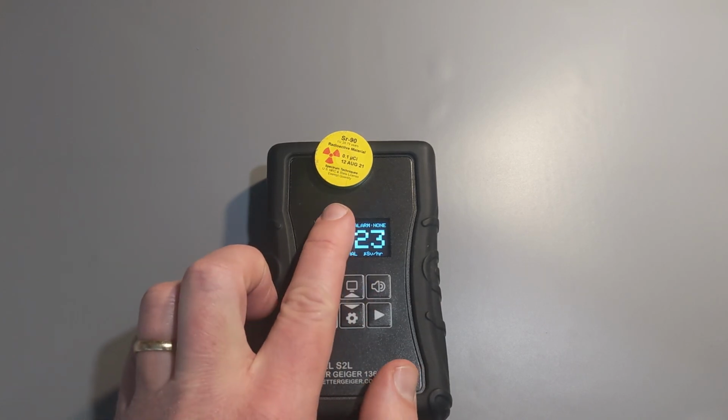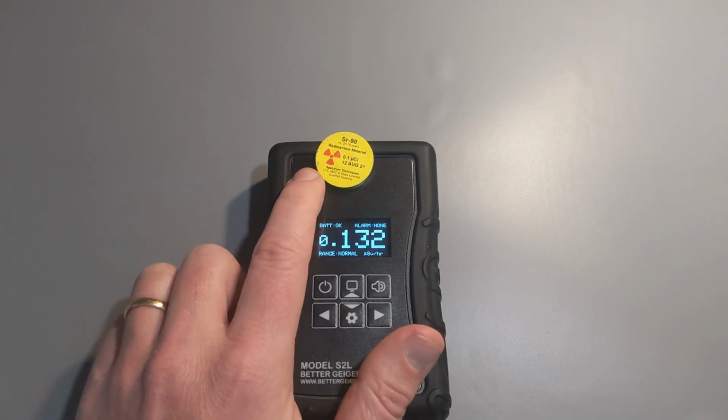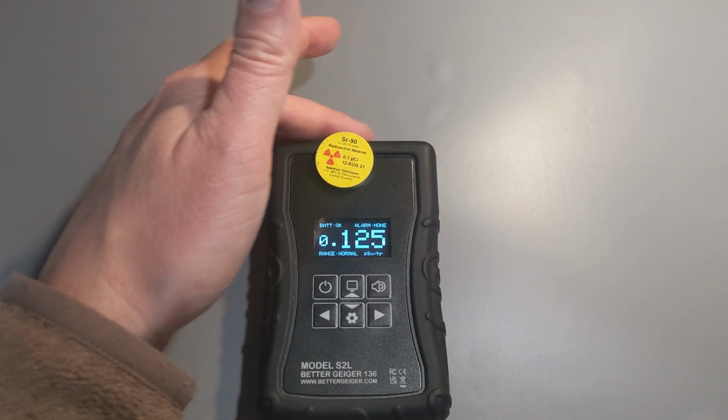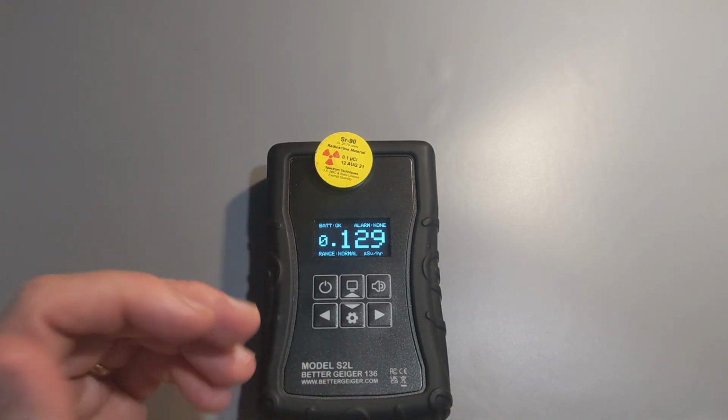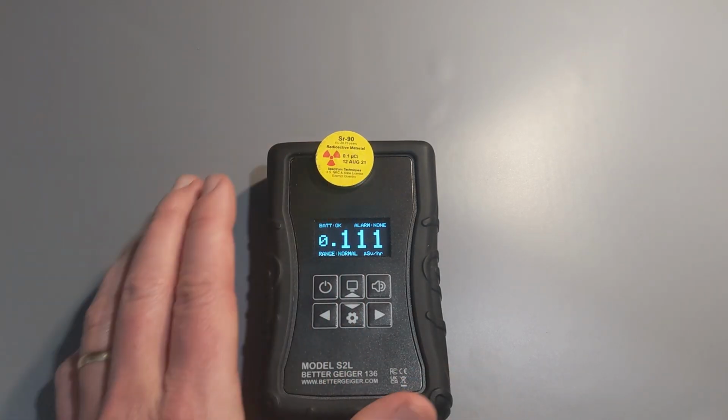Because it's simply shielding the beta, because this is meant to measure dose primarily. It's meant to measure X-ray and gamma. So it's got enough plastic and stuff around the sensor here to where those betas don't really penetrate, and so they don't cause a false overestimation of the dose rate.